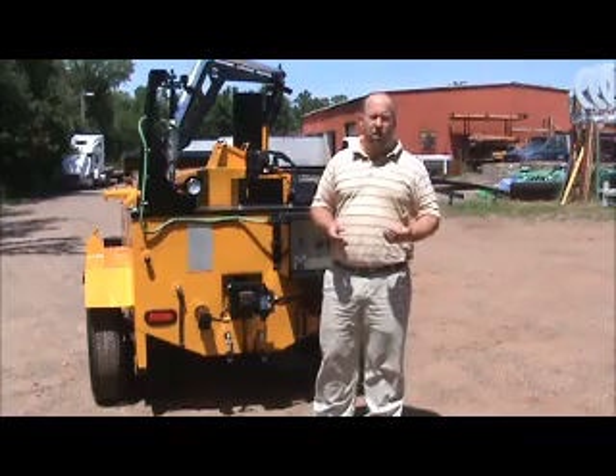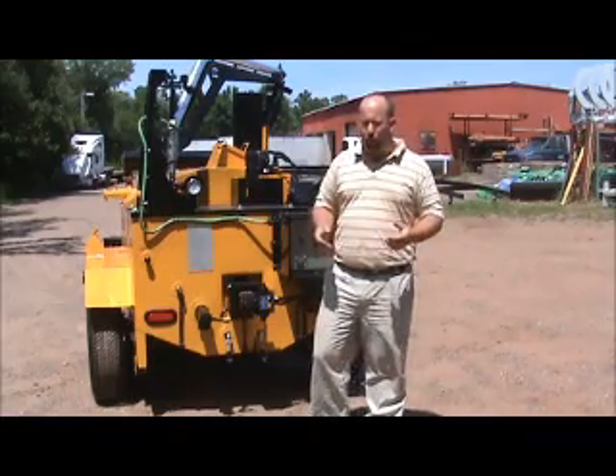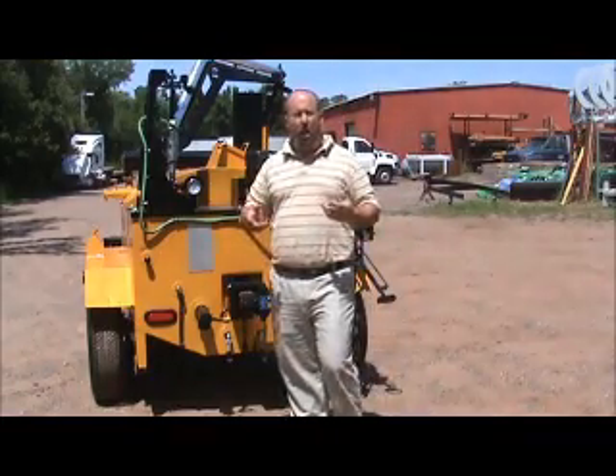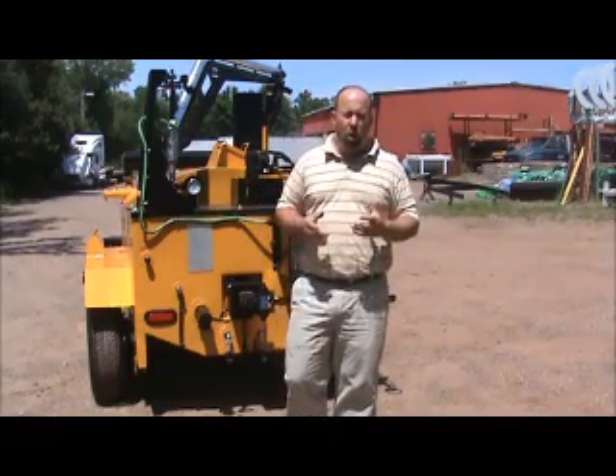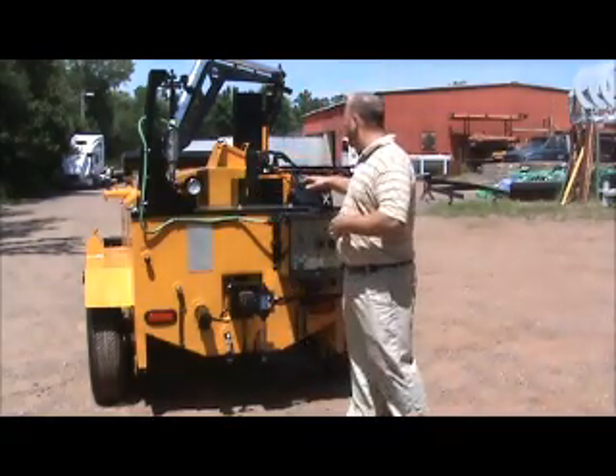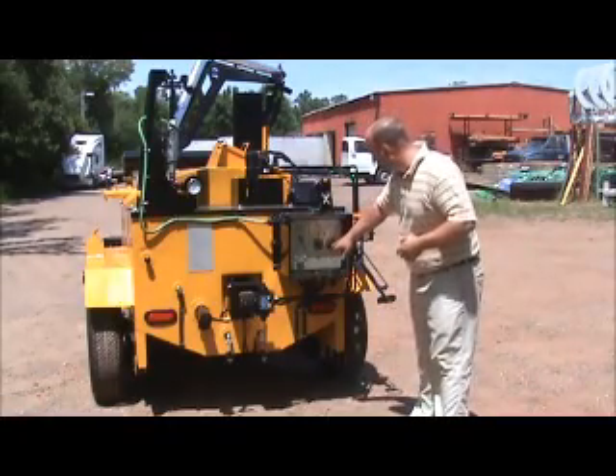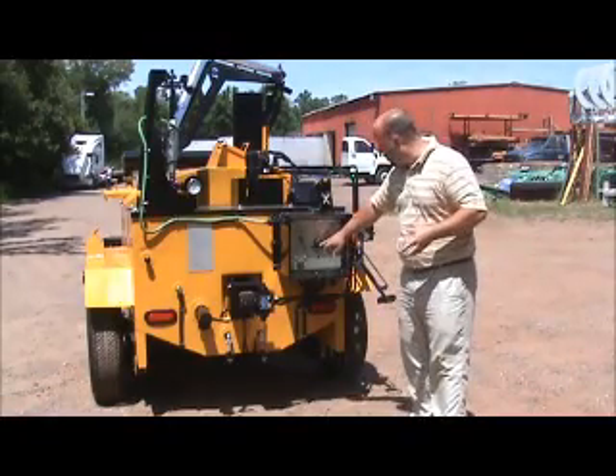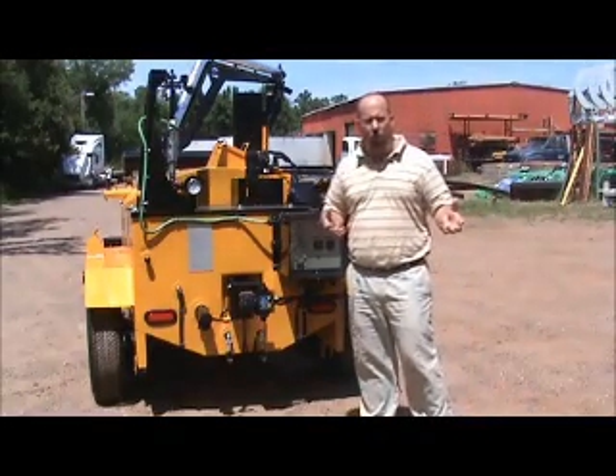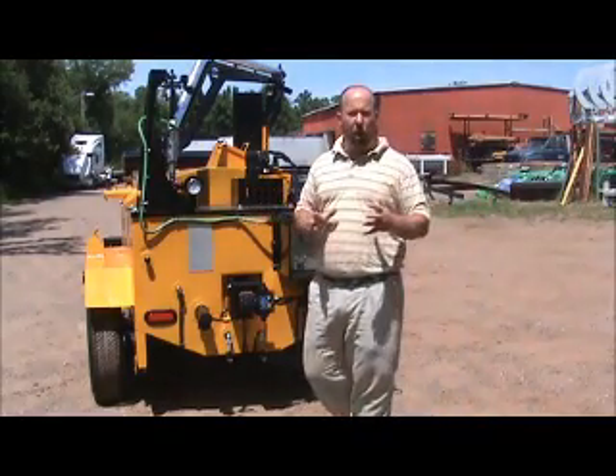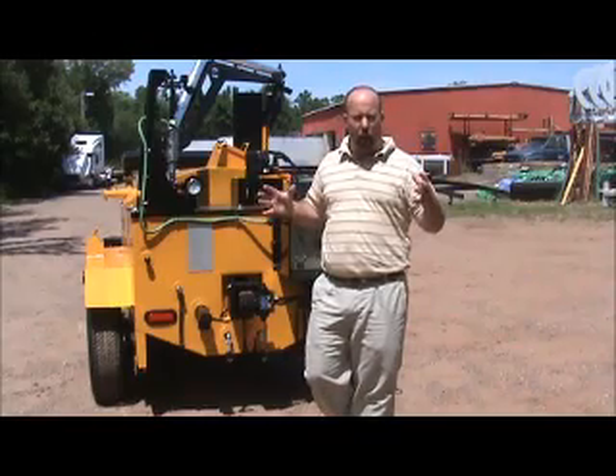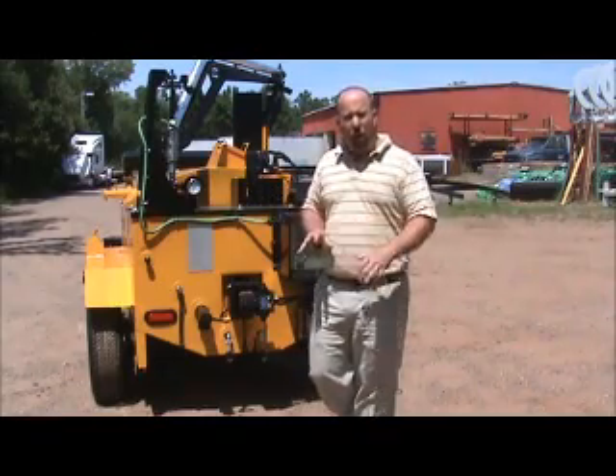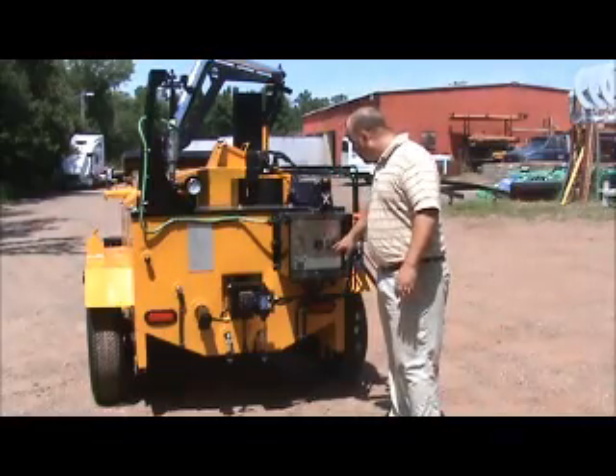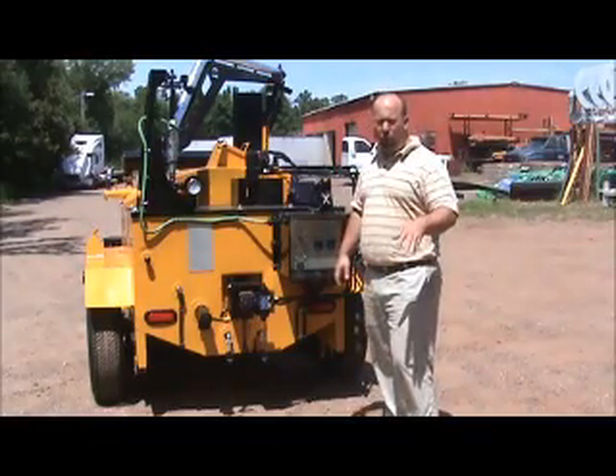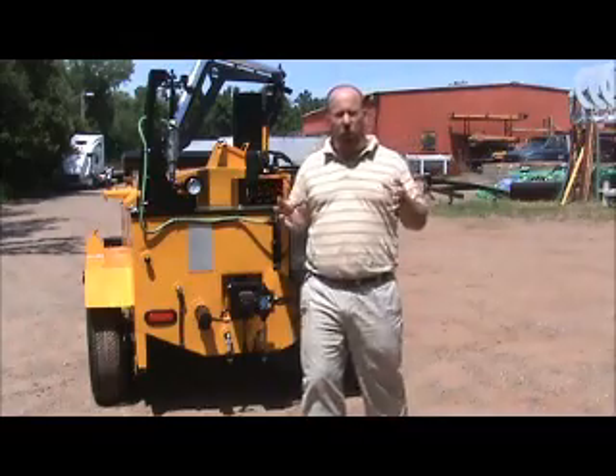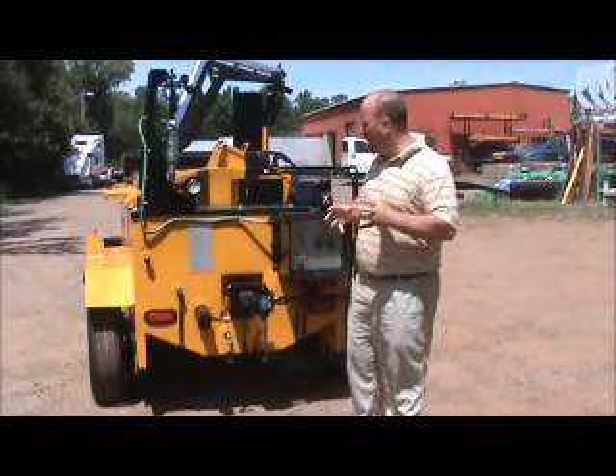Now when you initially fire this up in the morning and the kettle is cold, what you're going to see is the burner is going to come on until the oil comes up to temperature. Once the oil comes up to temperature, it's going to shut the burner off. And you're going to look over here and it's going to say your oil is 450 degrees and your product's 100 degrees. And you're going to go, well, why is the burner off? Because we're not using the burner to melt the product. We're using the oil jacket, or the heating oil, to melt the product. So on initial fire, you're going to see that oil come up to temperature and the burner is going to shut off. That oil is just going to soak the heat into the product, into the asphalt, and melt it.